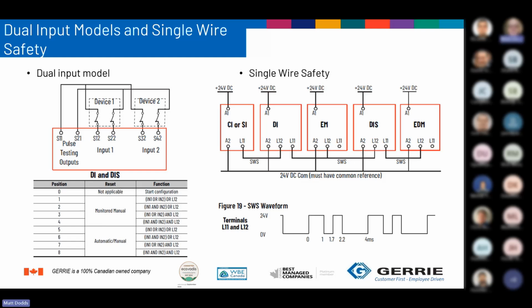So again, with the OR connected, I've seen these on load tables where I have parallel connected light curtains where at least 1 input must remain on at all times. So say the operator loads a part in, and then the robot comes from the other side, does something, and then the operator takes the part out. If they try to exist in the space at the same time, it would trip the output. In the past, you had to use 5 relays parallel connected. It was a mess. It's a setting with a dip switch.